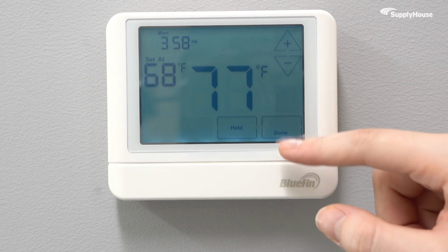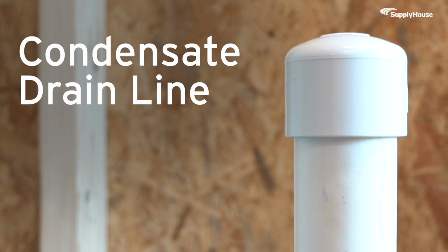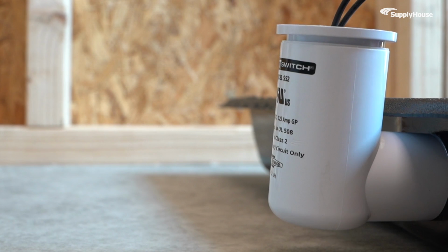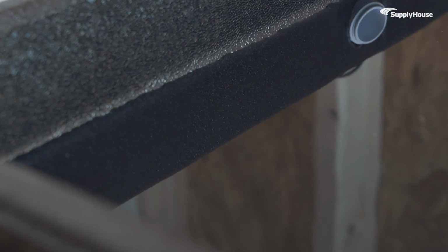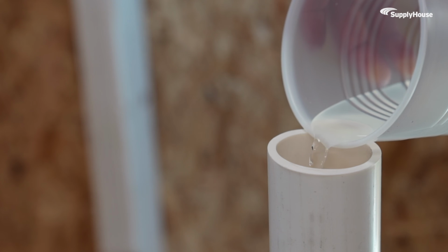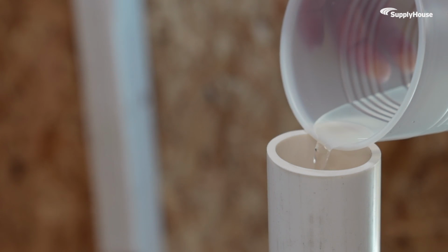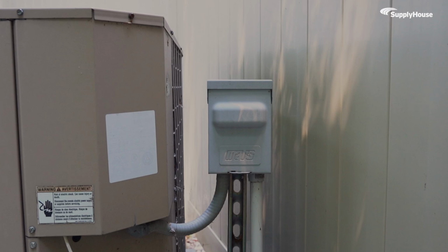It's also worth checking the condensate drain line. When the condensate drain pan fills up, usually from a clogged line, a float switch cuts power to prevent overflow. If you see standing water in the pan, that's your culprit. Flush the PVC drain line with a wet dry vac or distilled white vinegar. Clear the pan, and you should be back in business.